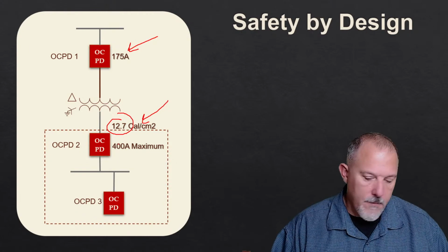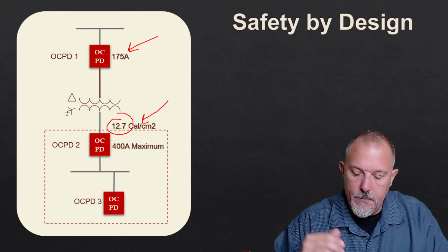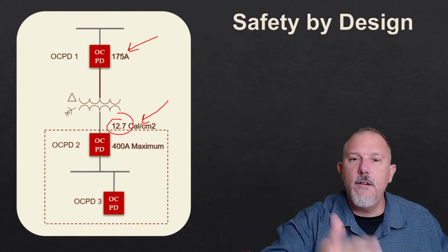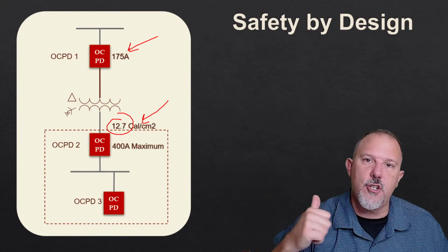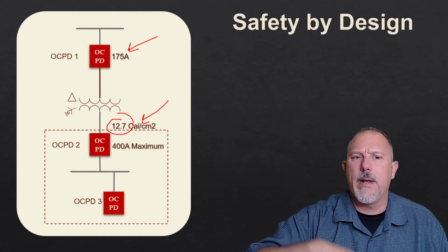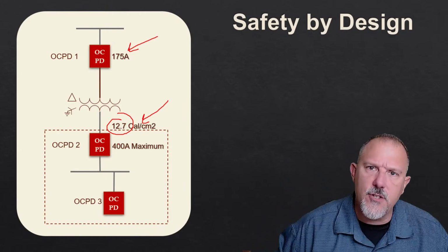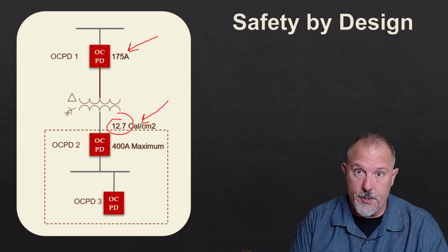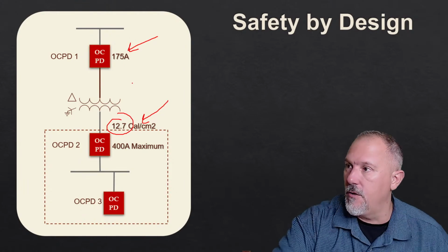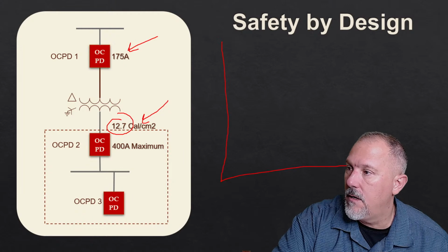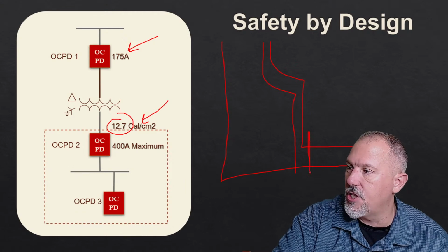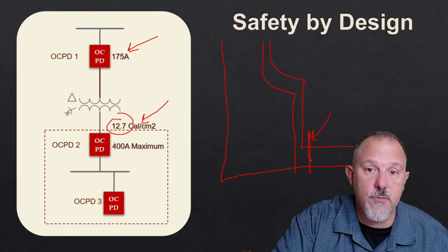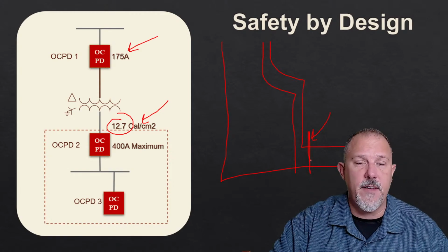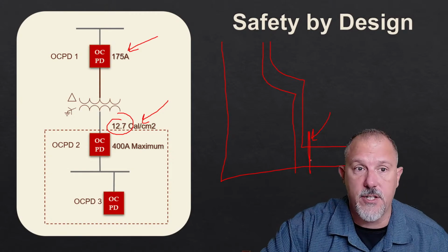Why do I say that? If you go to Article 450, 450 tells me I can go up to 250% on the primary of this transformer. What am I worried about when I pick the primary device on that transformer? I'm worried about inrush current. I'm worried about having a trip curve. I'm worried about that 175 amp circuit breaker that looks like this having an inrush current in the instantaneous region, causing that 175 amp breaker to trip every time I energize the transformer.